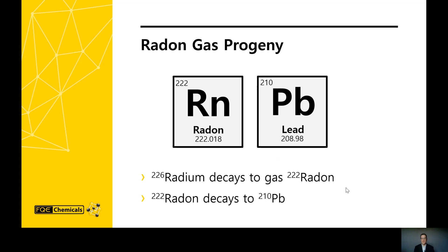Radon-222 is the intermediate decay product of radium-226, and it preferentially follows the natural gas lines. It decays through several rapid steps to lead-210, which can therefore build up as a thin film in gas extraction equipment. Radon typically follows the gas stream, and in the absence of natural gas, radon will dissolve in the hydrocarbon and aqueous phase.